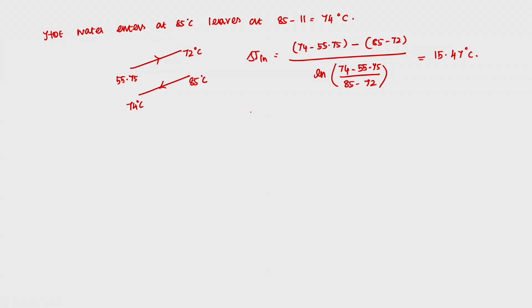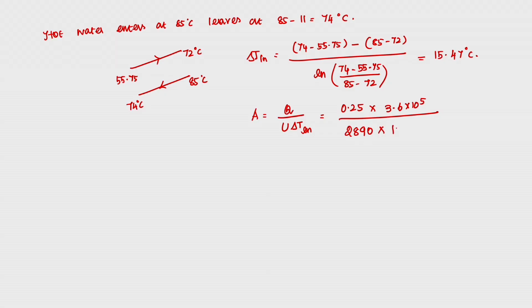So, we already know that A is Q upon U del T ln. So, Q is 0.25 into 3.6 into 10 to the power of 5, 25% of the total heat requirement. U is given for hot water, 2890 watt per meter squared Kelvin, and the logarithmic mean temperature difference is 15.47. So, your area is coming around 2 meters square. So, number of plates is 2 upon 0.79, which is coming around approximately 3 plates.